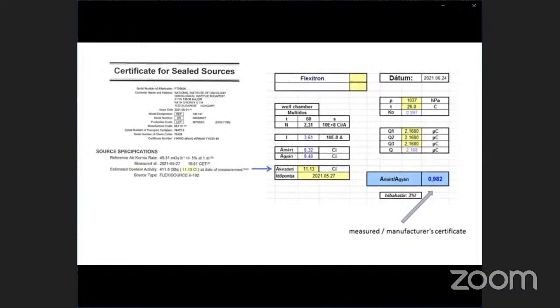The reference activity or air kerma rate is read from the certificate for the sealed sources on the left side. And using the special Excel sheet, we can enter the measured charges. We can enter the reference air kerma rate, and we have to enter the date of the measurement. And from these data, we can calculate the current source activity.